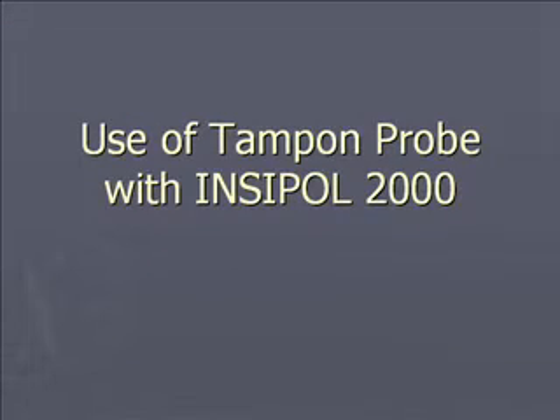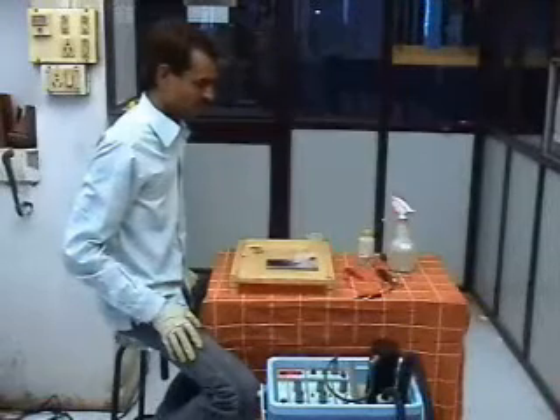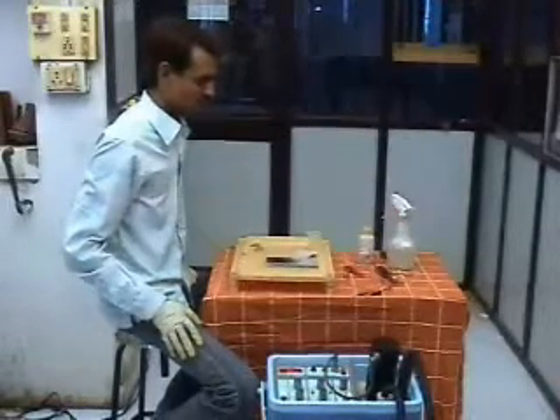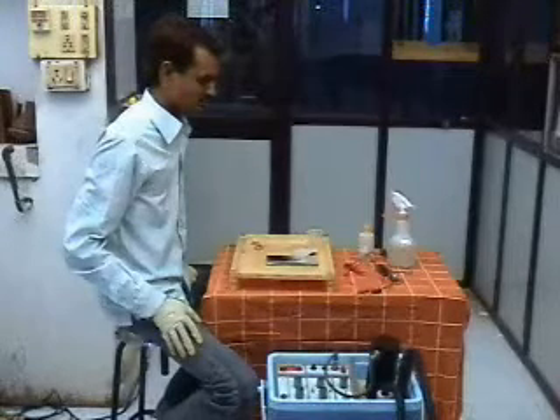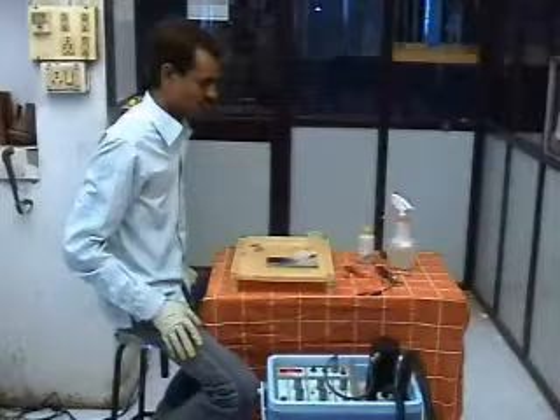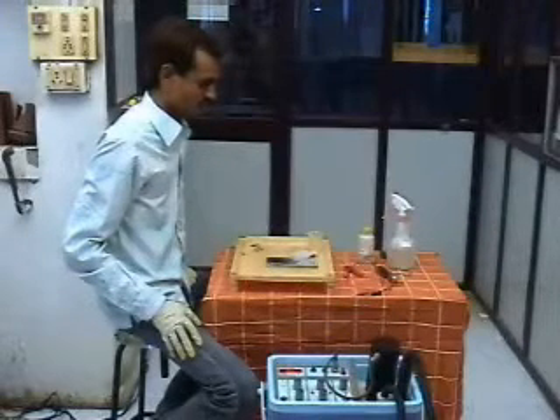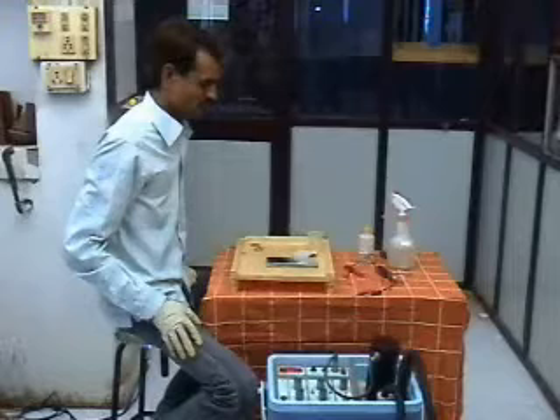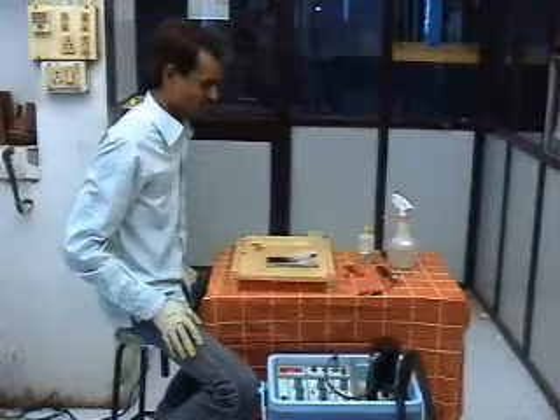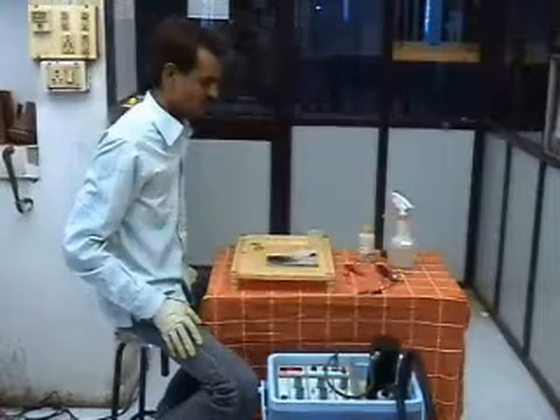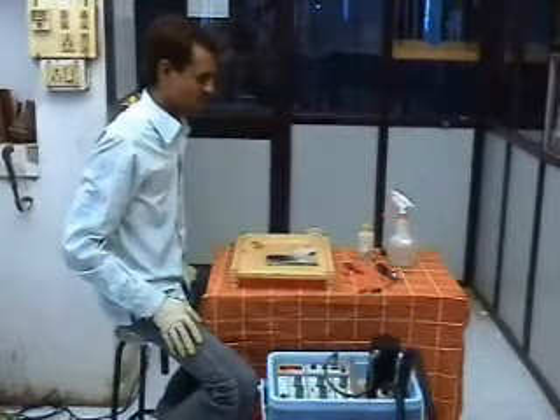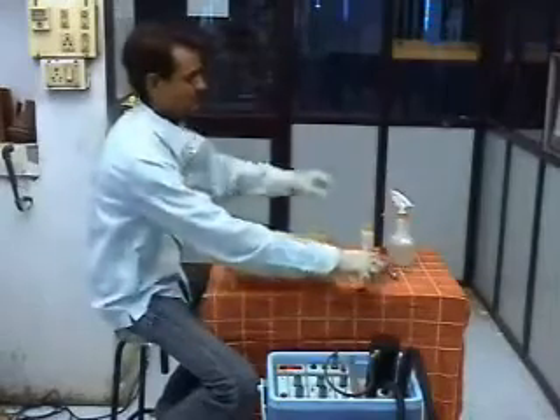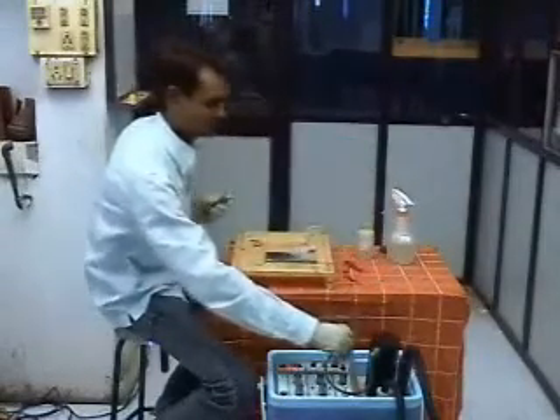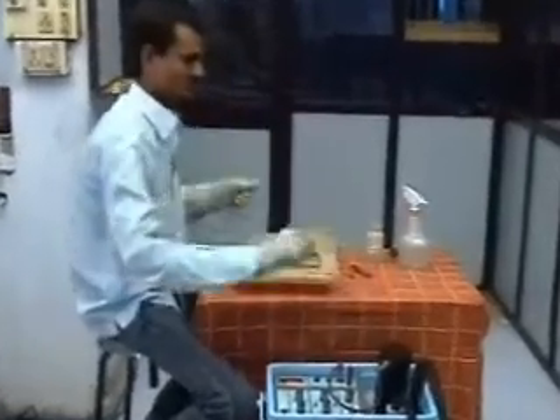Normally, as far as possible, use circulatory flow technique with INSIPOL as it is skill free and even standards recommends the same. If more area needs to be covered, then use tampon method as it is skill based process and a care is involved. Connect the tampon probes to the machine. Connect the anode, that is sample, with crocodile pin.